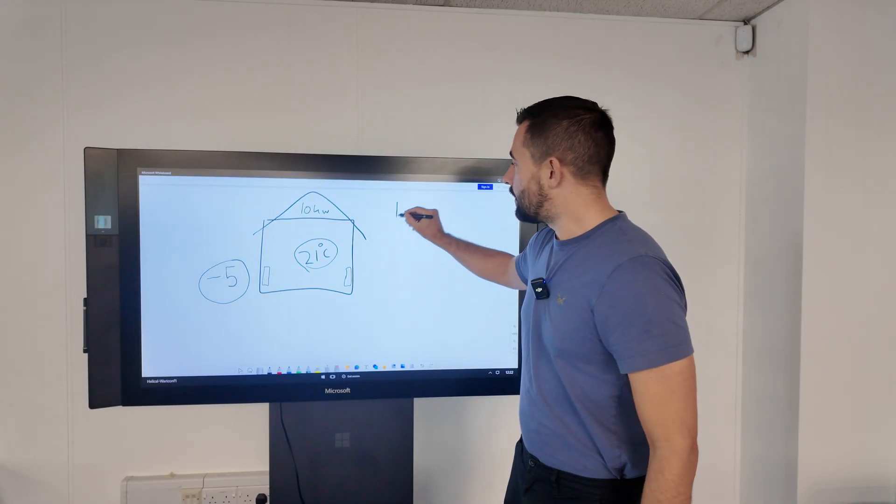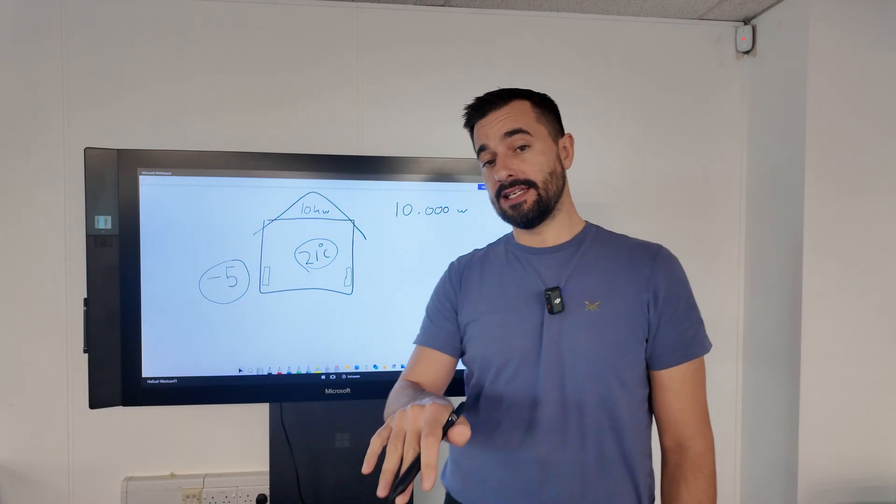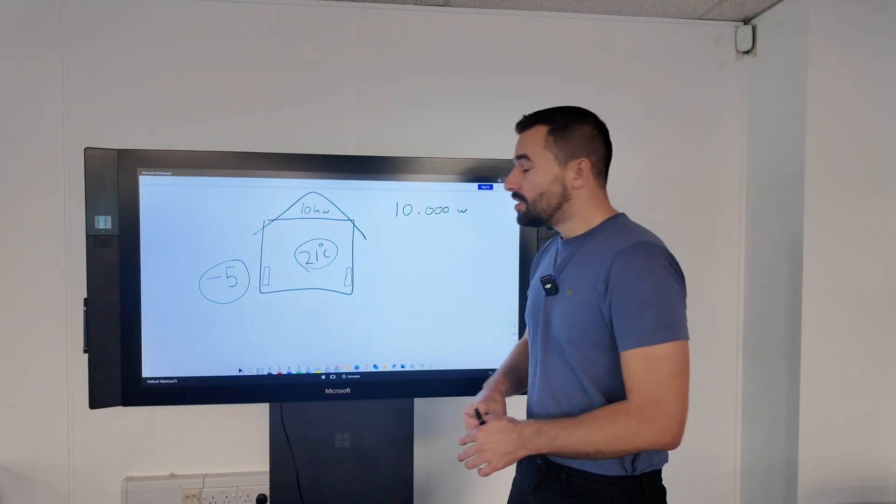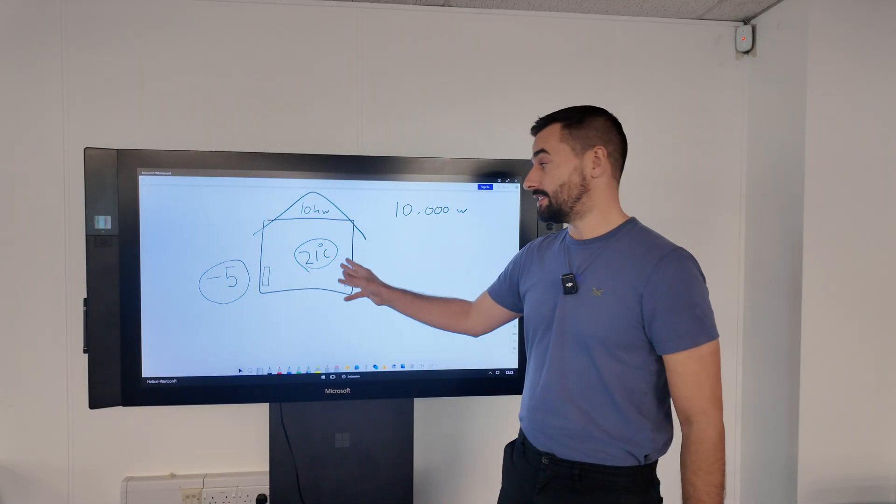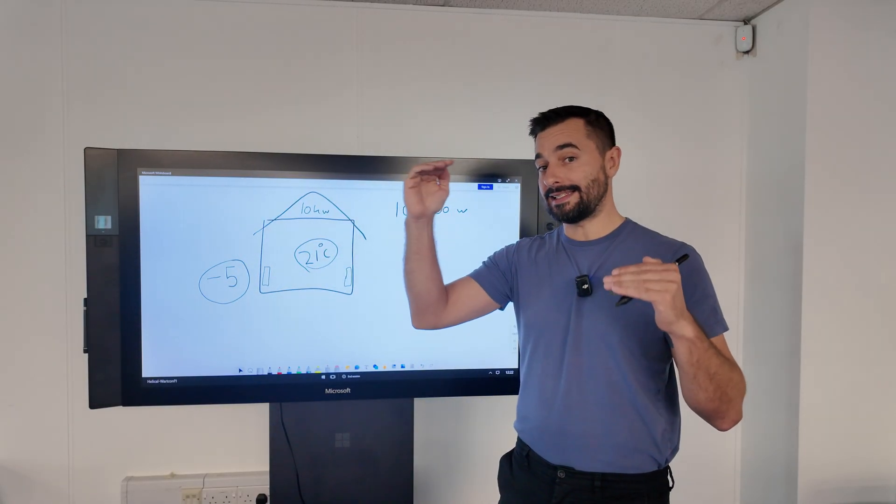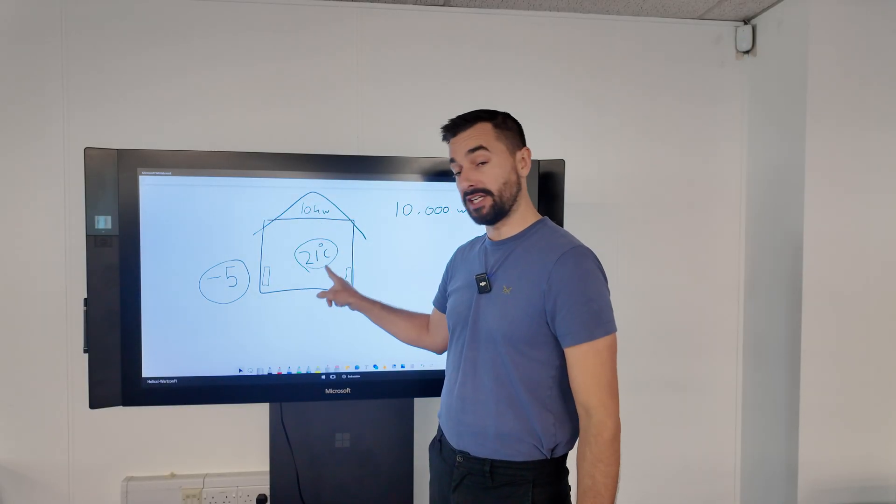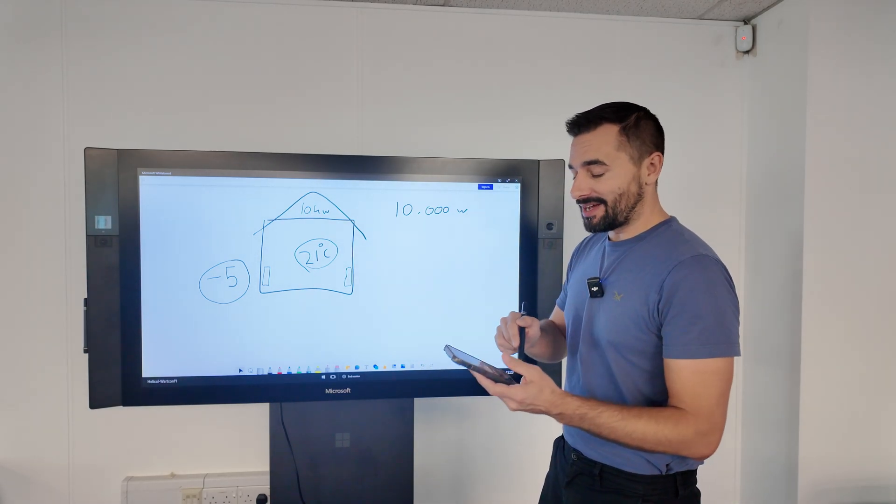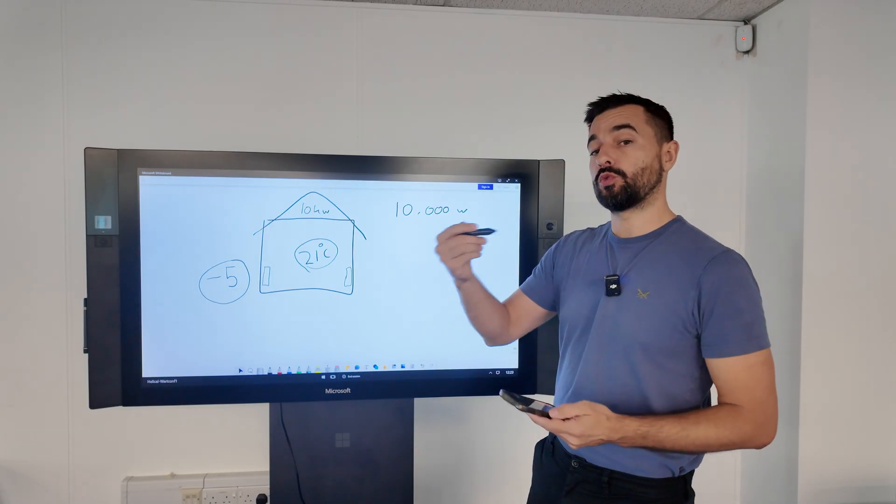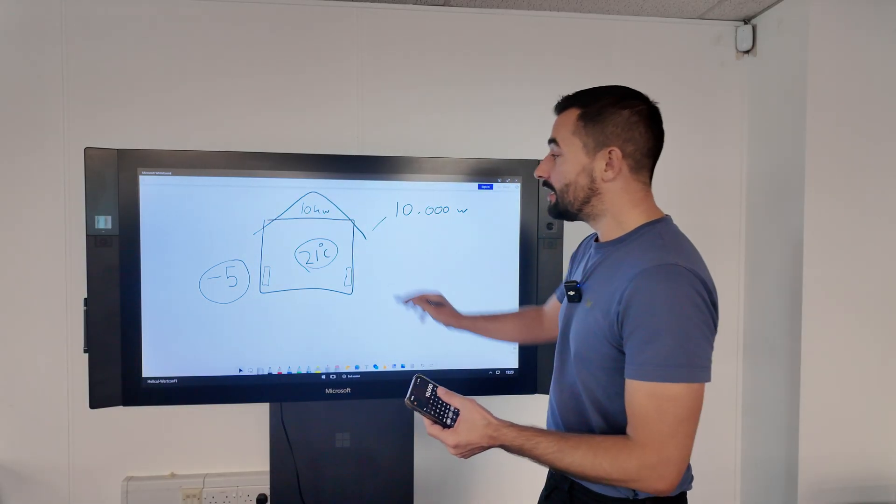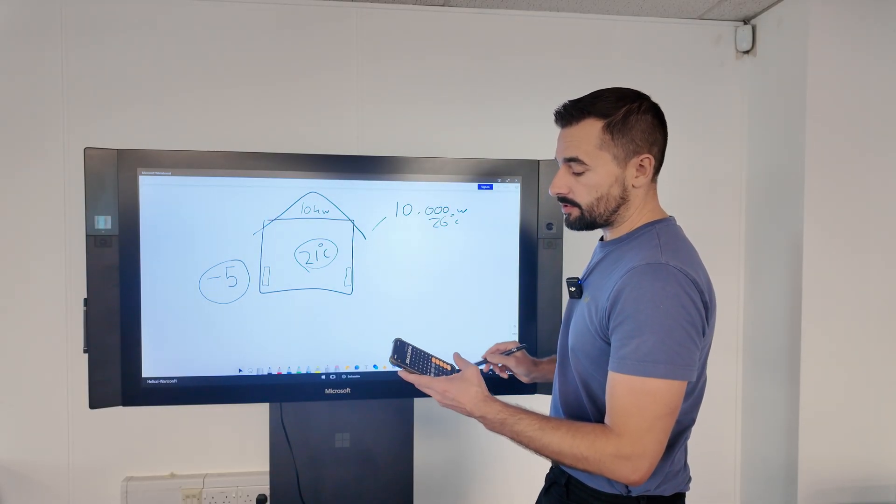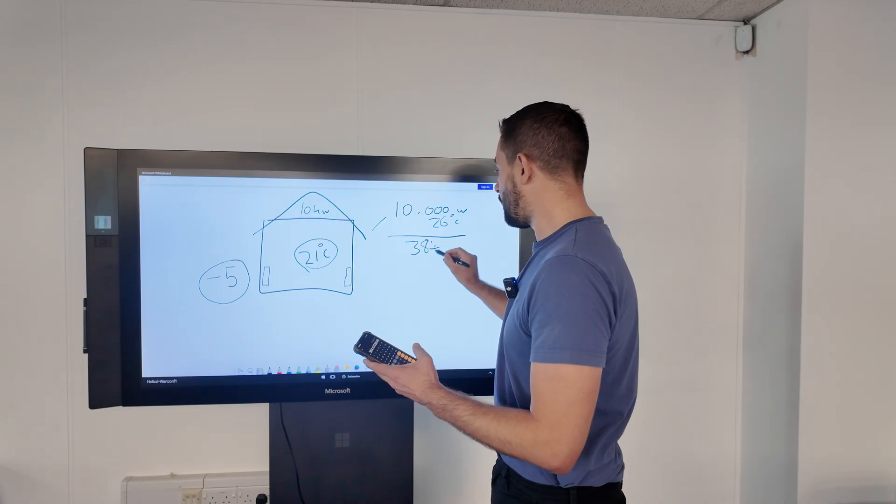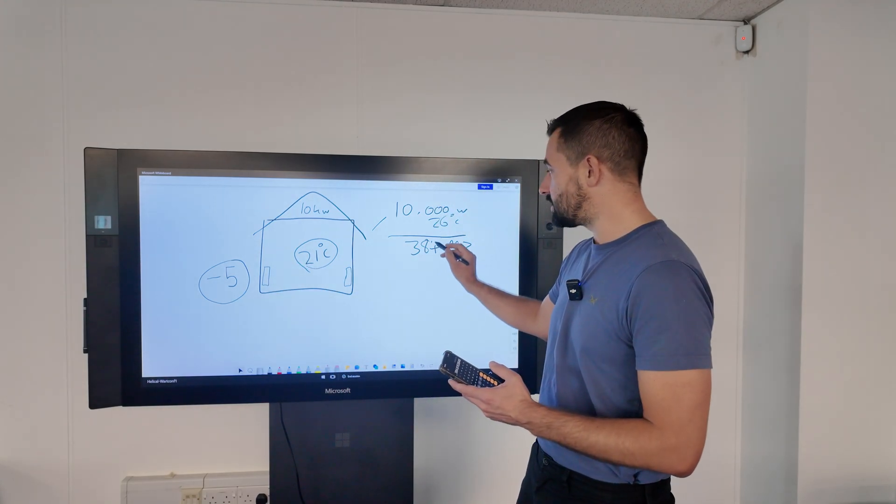What we can do with that is work out how many watts heat loss we have per degree of temperature change from outdoor to inside. If we just slow it down a bit, the difference between the indoor temperature and outdoor temperature is 26 degrees in this situation. We've lifted the temperature from minus 5 to 21, which is a 26 degree differential, and we needed 10 kilowatts to achieve that, or 10,000 watts. So we can divide that wattage using my calculator to work out how many watts we need per degree rise. If we take the 10,000 watts and divide it by the 26 degree differential, that will give us 384 watts per degree rise. For every degree difference, we needed 384 watts.